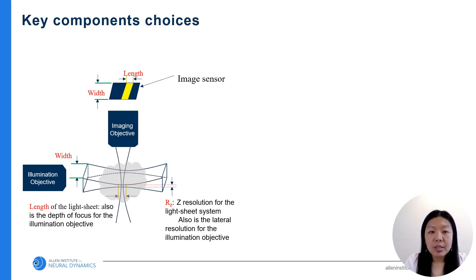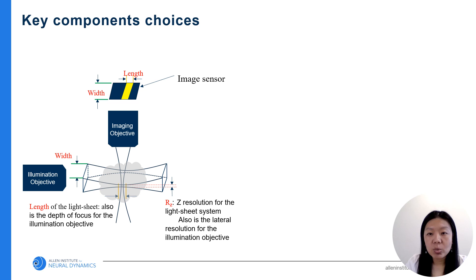This is a simplified illustration of a SPIM system, or light sheet system. The X and Y resolution are defined by the imaging objective and the camera. The Z resolution is defined by the illumination device. The maximum sample size is decided by the working distance of both objectives.